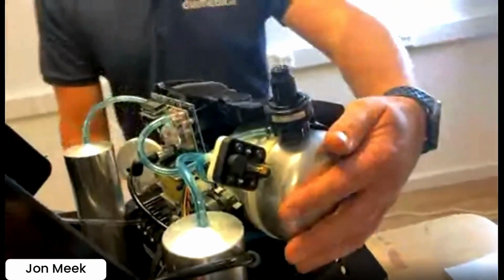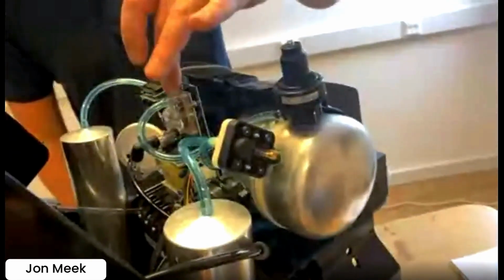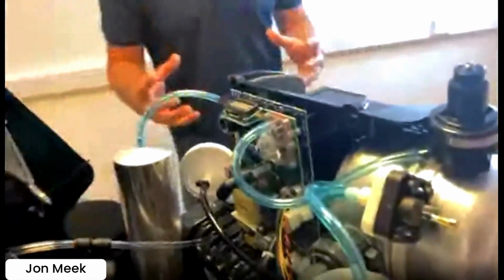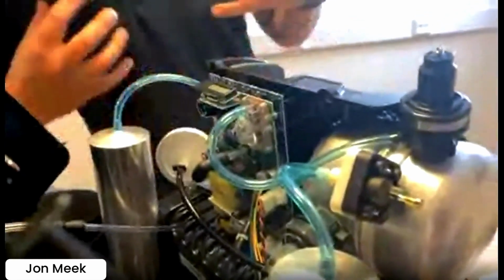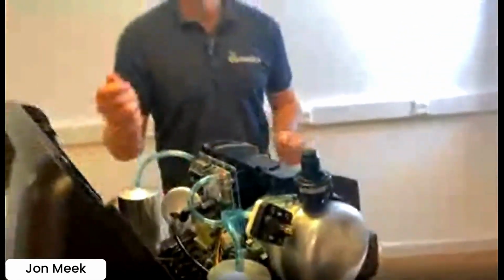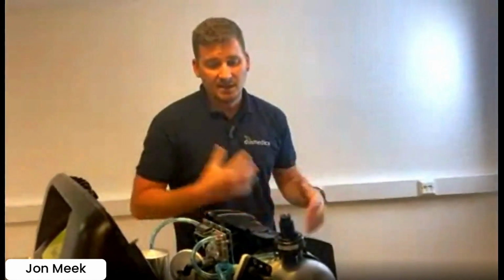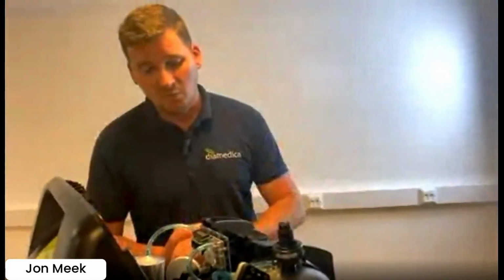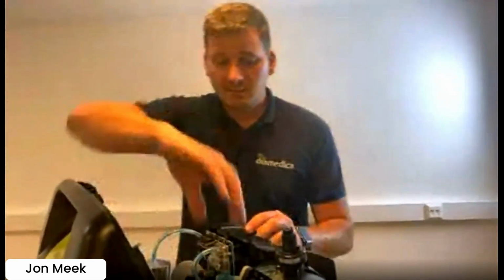Once it comes out of your accumulator tank, it then goes through your circuit board, which has at the top there your analyzer cell built into your board, which are long life cells. And that was another thing that was really important. We needed to use a long life cell rather than ones you have to replace every 3 to 6 months. Again, reducing the cost of the overall running of the machine. It comes out of your circuit board through another HEPA filter, the same as the air, but we're going the other way now, down through to the compressor.